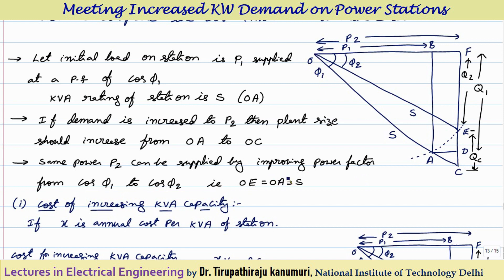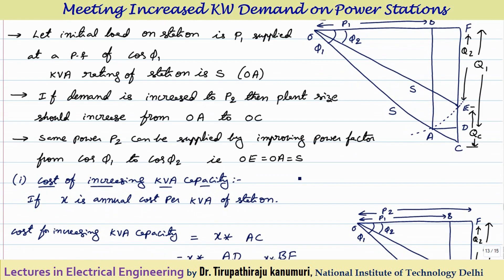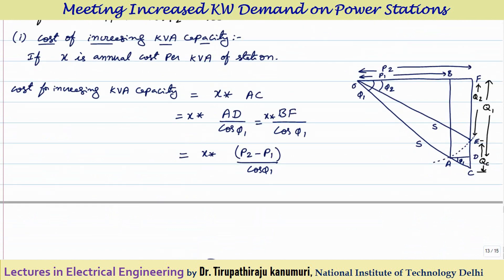AC will be the extra capacity that should be increased. The same power P2 can also be supplied by improving the power factor — the same KVA rating intersects at point E by improving the power factor from cos phi 1 to cos phi 2. OE = OA = S, unchanged, by installing power factor correction equipment. Now, for the cost of increasing the KVA capacity — that is AC — if X is the annual cost per KVA rating of the station, then the cost for increasing KVA rating equals X multiplied by the extra KVA required, which is AC. Since the angle is phi 1, AC = AD / cos phi 1.